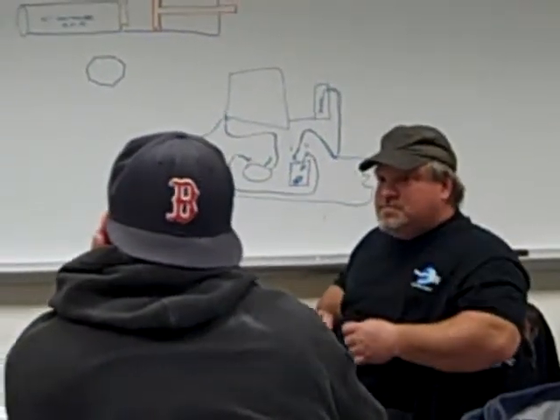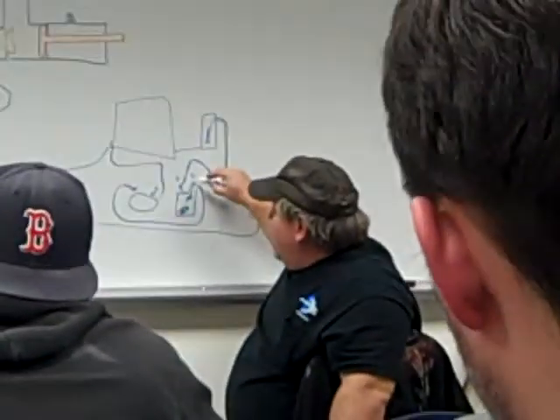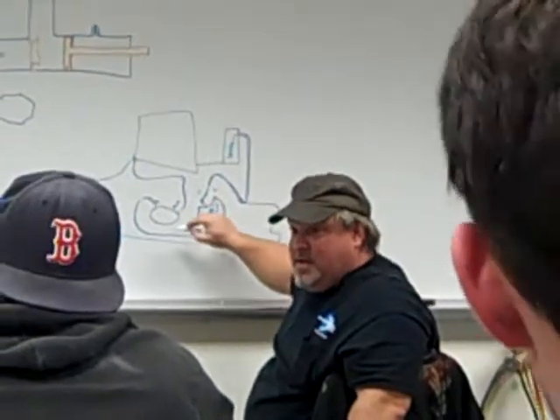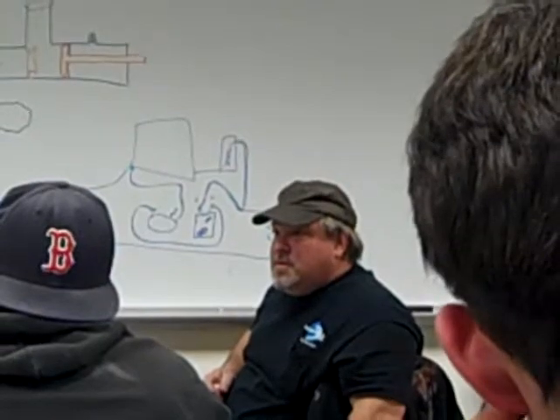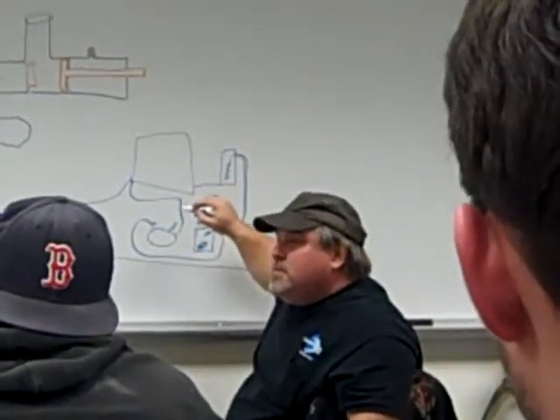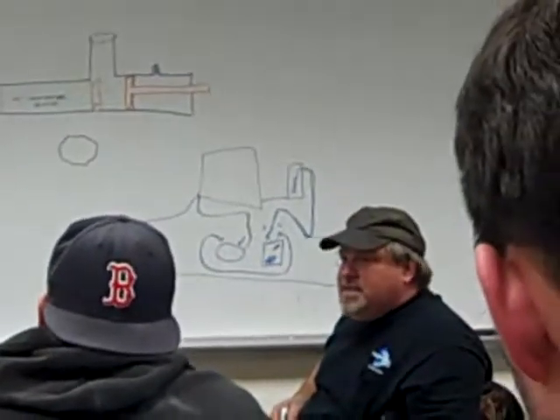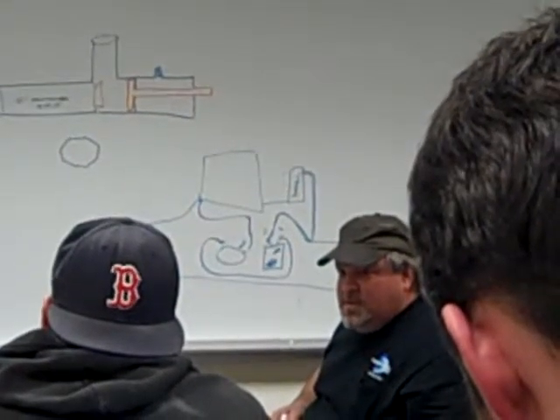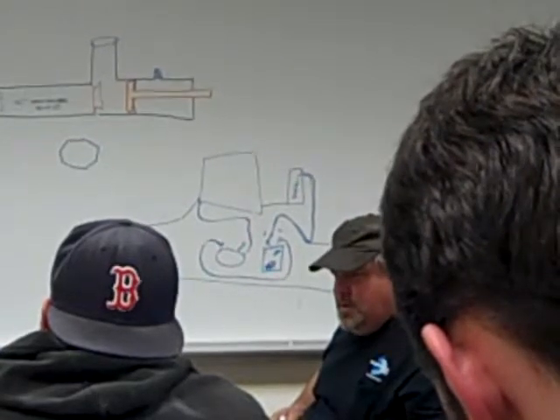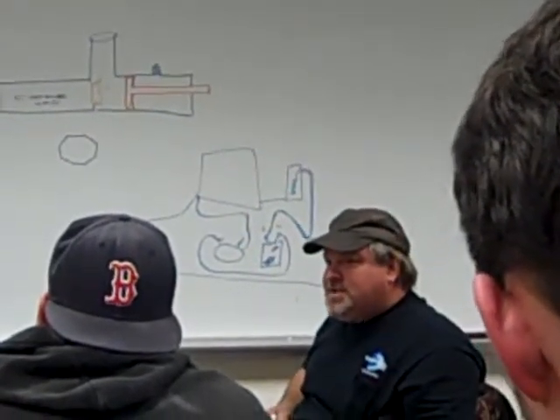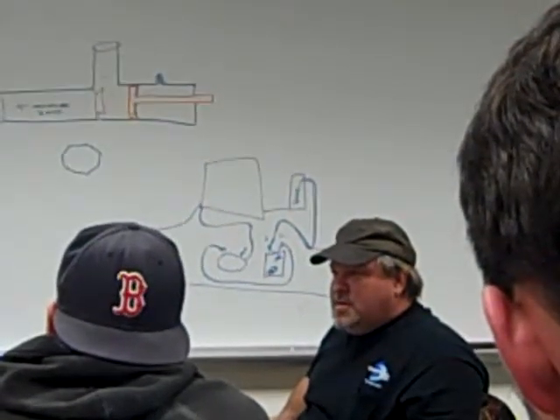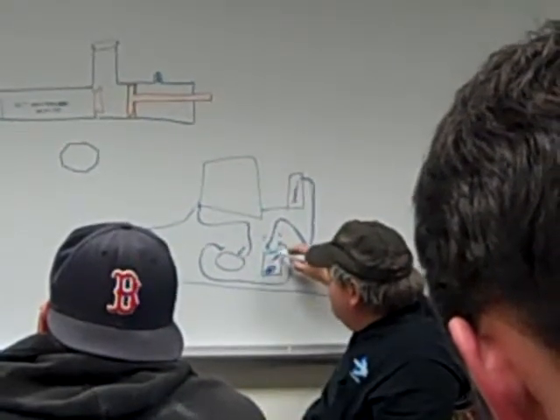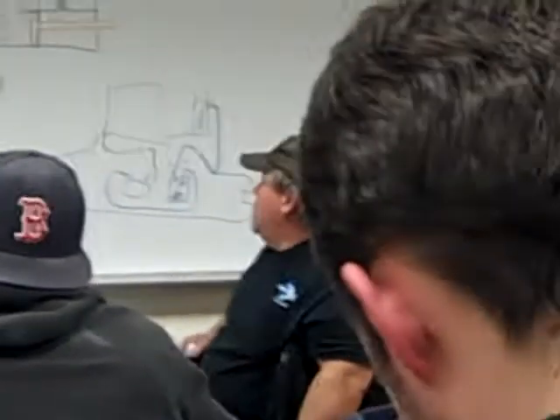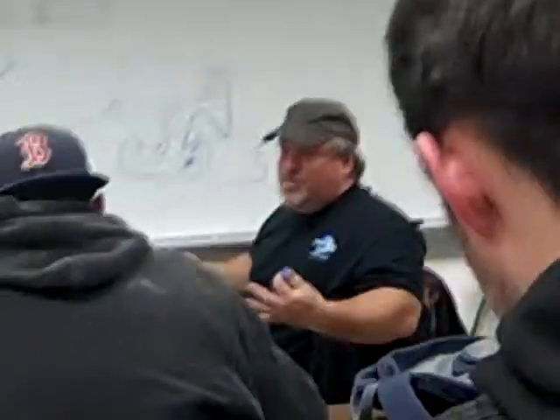Why wouldn't you do it the opposite on the tank though? No, because you want this to be vapor. You don't want to be pulling liquid out of your tank. Yeah, but on the high side, I thought we should do the vapor side of your tank. No, the high side is liquid. The red side is liquid on your tank. Is it? Yeah. I thought it was the other way around. Pretty sure. We'll check and see. I'm pretty sure the high side is liquid on your recovery tank. I'm not positive myself on it, I've never been positive on it. Yeah, I'm pretty sure the high side has the tube that comes down in, and the low side is just off of the top of the tank. Okay. Yep. But that's the method, it's called a push-pull method. And there may be questions on the test about that too.